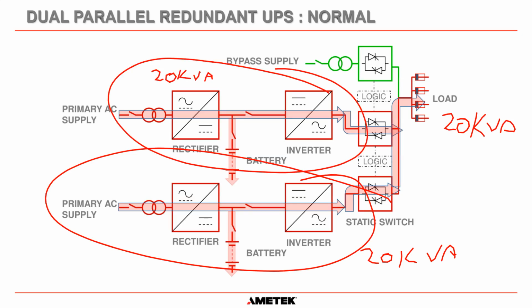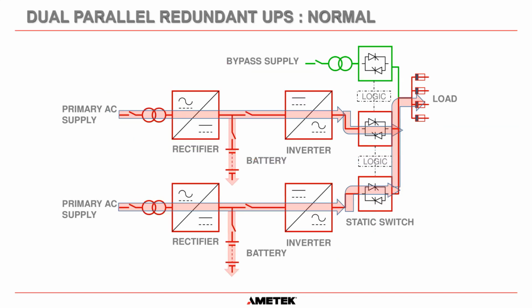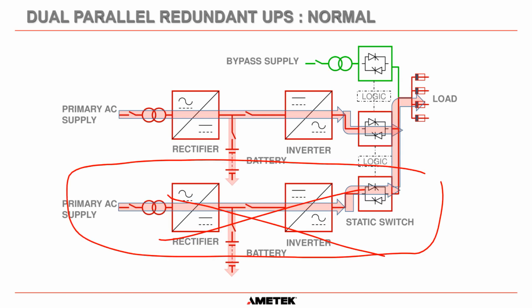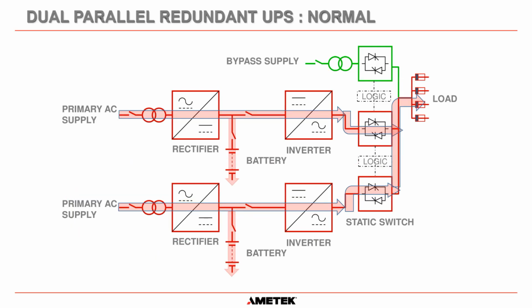Because when it's parallel redundant, what we want to do is if this UPS here doesn't work anymore, we want this UPS here to be able to continue and supply the full power to the load. So both UPSs have to be rated to supply power to the loads. Okay.